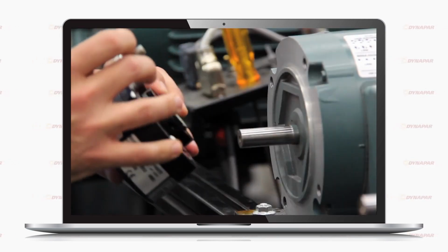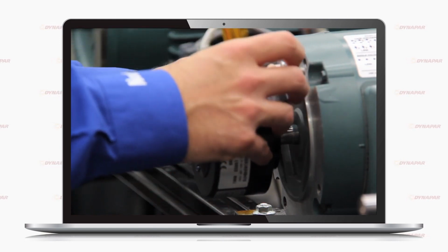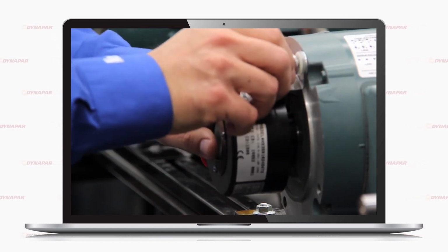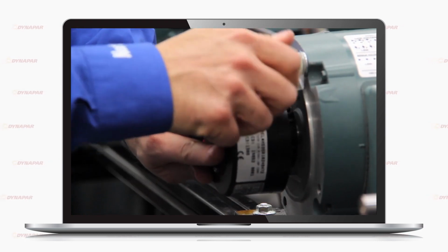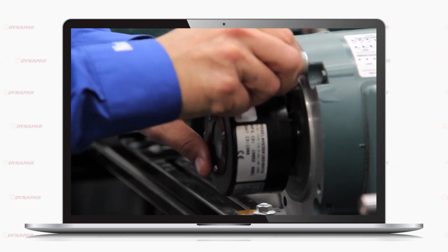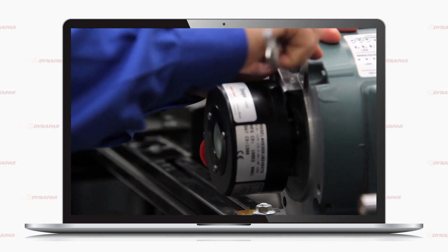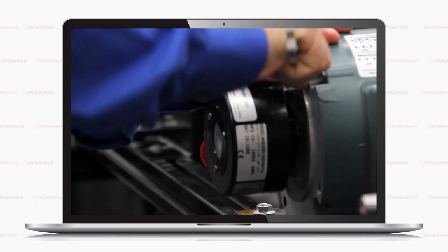To help prevent the needless rip and replace of a functional unit, the HS35iQ encoder monitors its internal position sensor's health. This feature tracks the health of the internal LED within the position sensor and issues a warning to the user when the LED is nearing the end of its life.